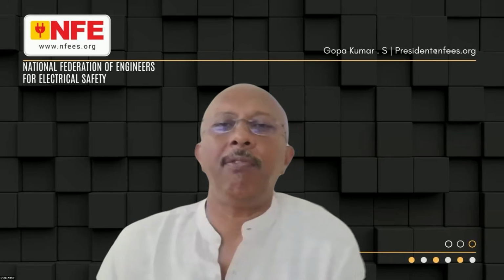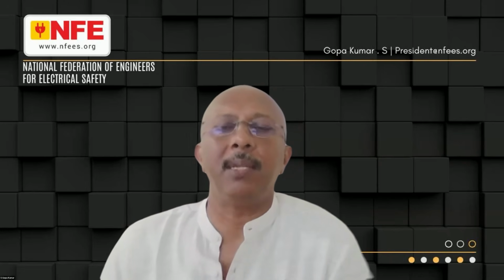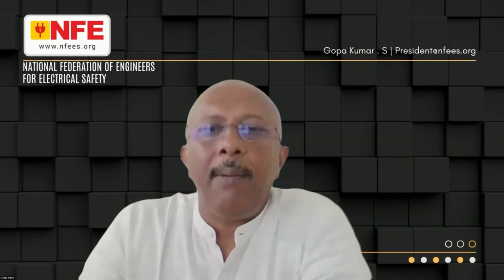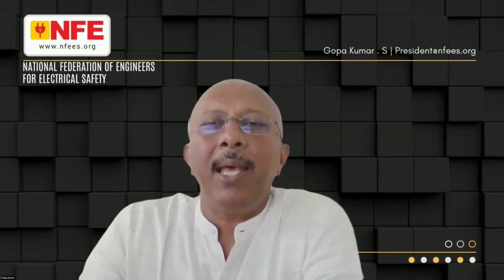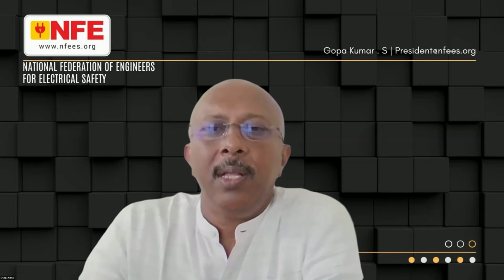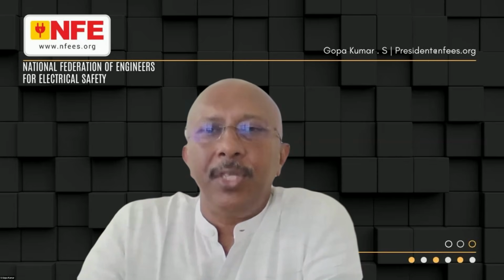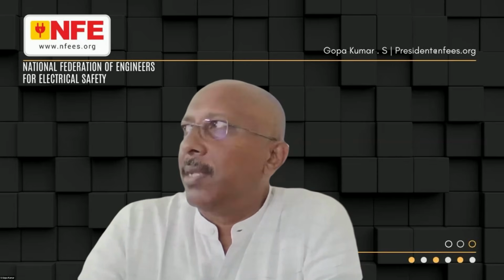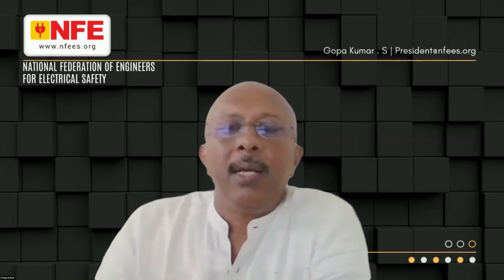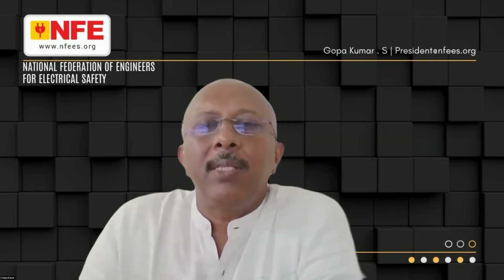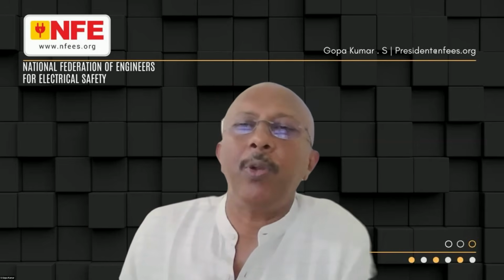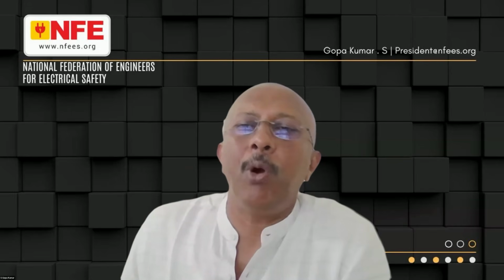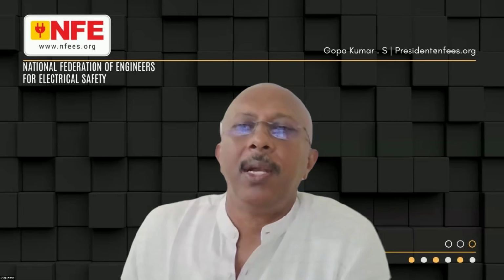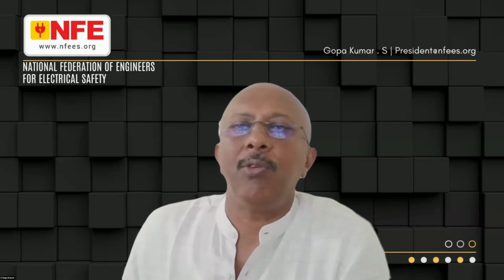Mr. Janardhan is asking about the effect of a lightning arrestor on the nearby electrical system earth. Of course, the lightning protection system must be bonded to the metallic parts of your building. It is a must. The idea here is, if you have two different conductive systems, there can be a potential difference. But you must ensure that the lightning protection system as well as the electrical system are interconnected in such a way that there is no potential difference. So it's always about how to avoid potential difference, or how to create an equipotential bonded system. That means during lightning, there is no potential difference. As a result, there is no failure.